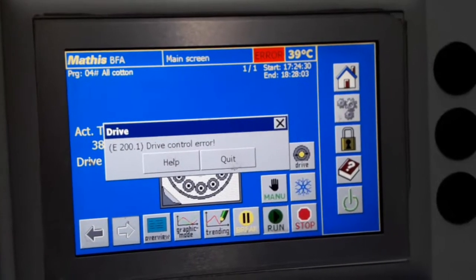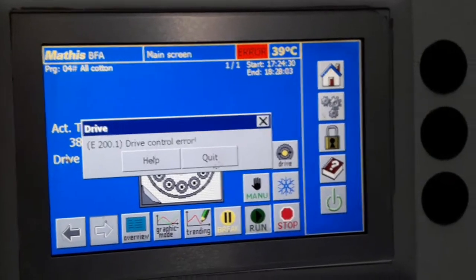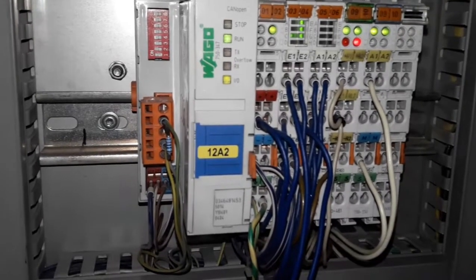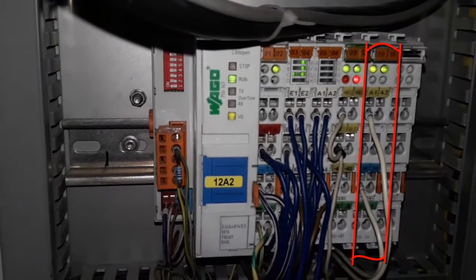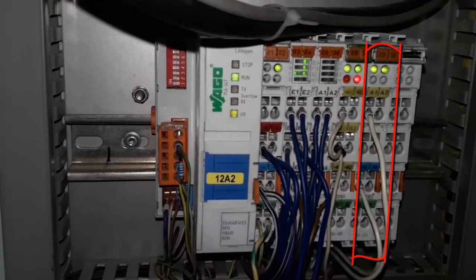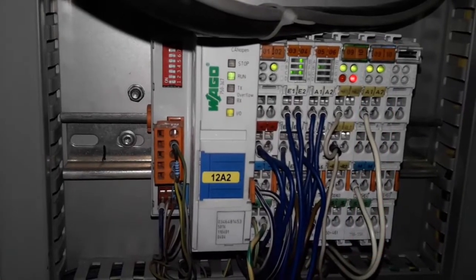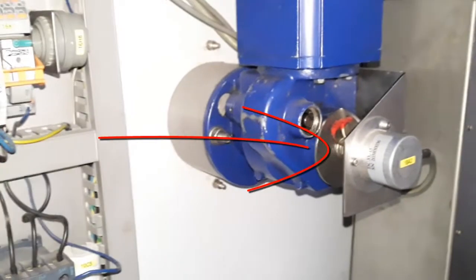Drive control error in a lab dyeing machine. This unit uses a WAGO PLC, and the analog output card is damaged. The inverter receives the run command but does not receive a frequency reference, which is why the motor is not rotating.